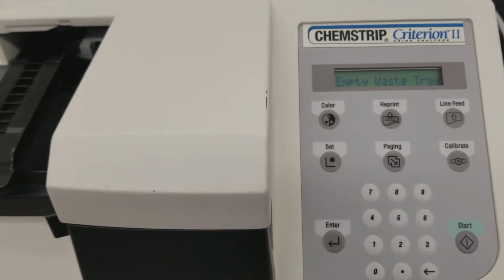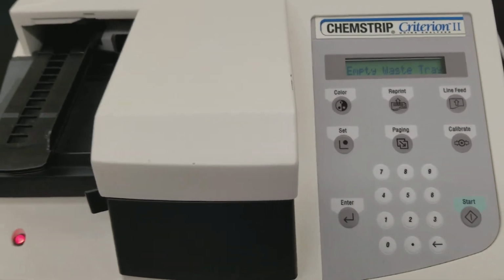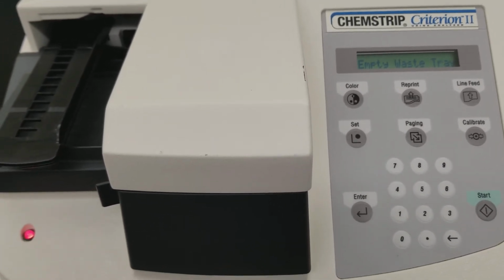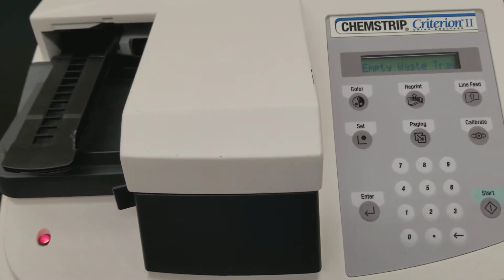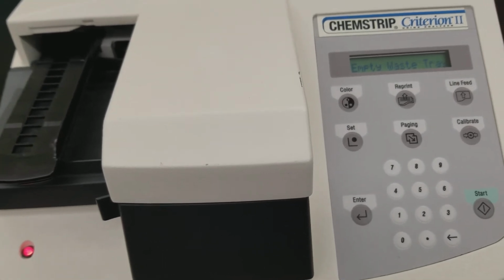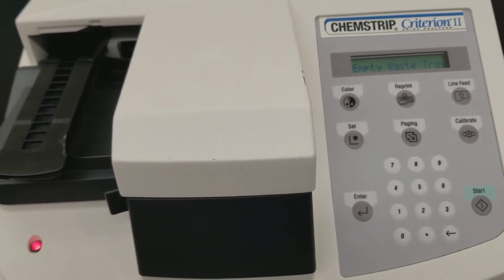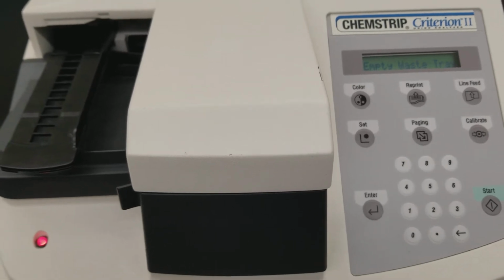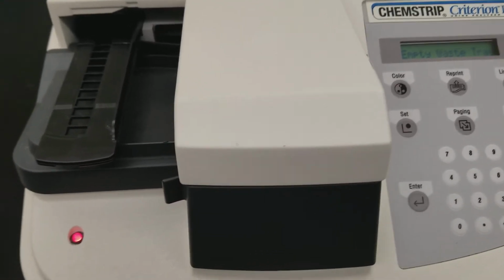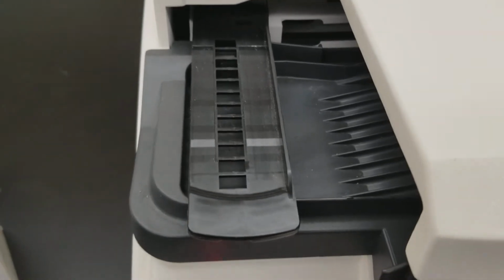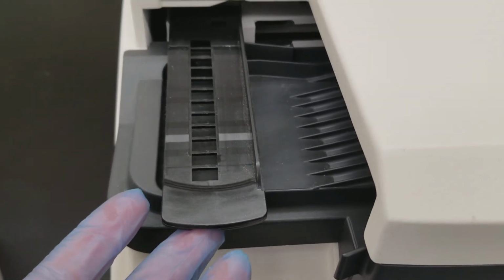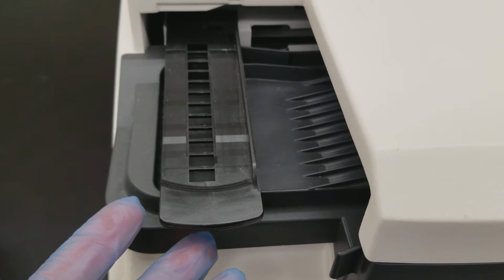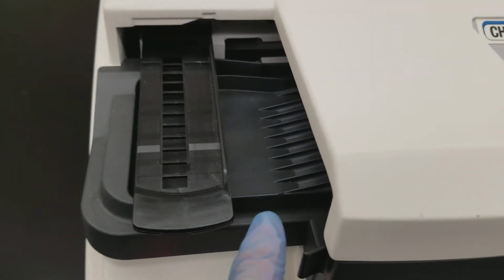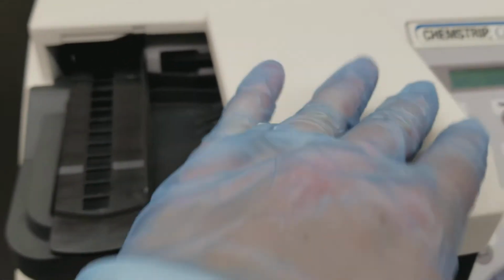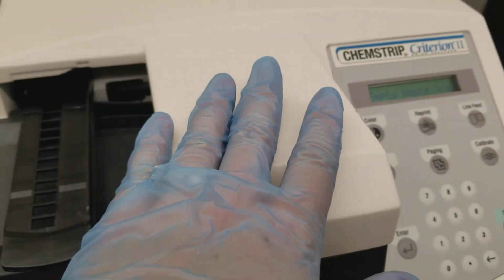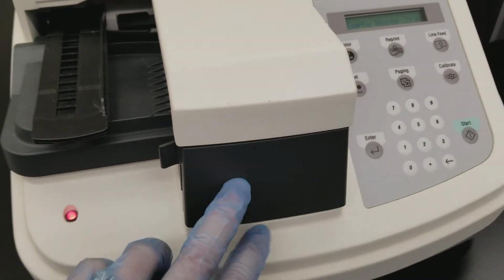It's saying empty the waste tray, and this is something that it's always going to ask you to do when it first starts running. This is the part where I want to make sure that you're doing things that are not going to break the analyzer, because again, I cannot get any more parts for this. The part that always ends up breaking is this. This is the strip feeder, and when you put a strip on here, it moves it along into the reading area of the analyzer before it trashes it into the waste bin.